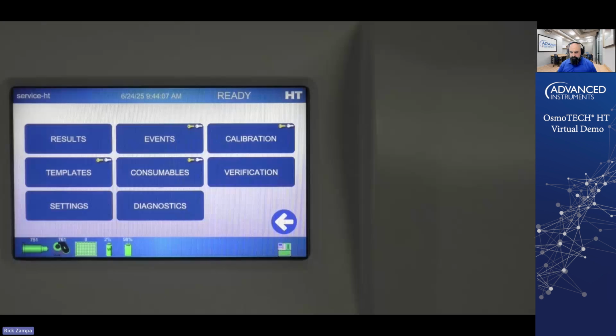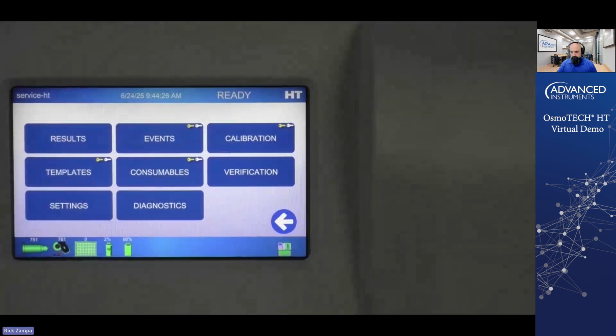Important thing to understand, calibration is required only once per year on our instruments. These instruments are very, very stable and robust. We don't expect the calibration to go out of range. It would probably be done when you do your PM every year on the instrument. That would be the most common time to do that. Whoops. So let's go back there. We talked about calibration and verification. Oh, the other thing, I'll do it in another menu when I have other things.